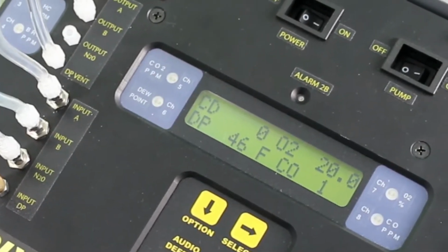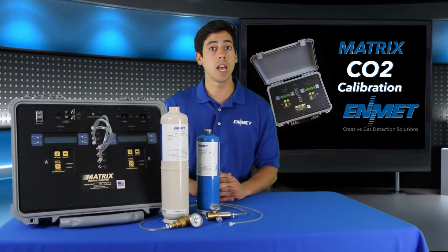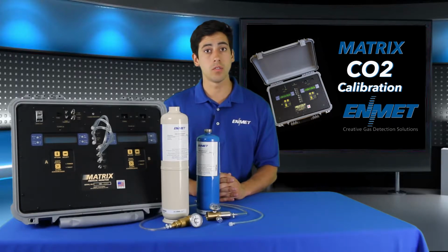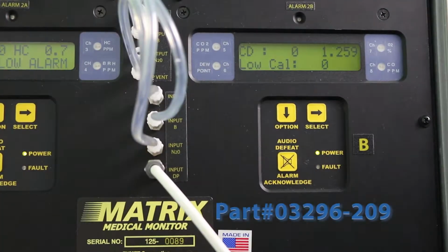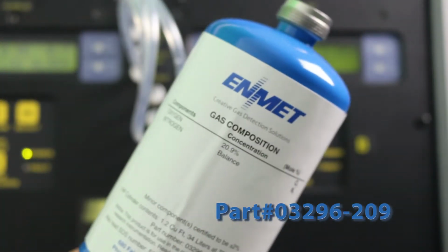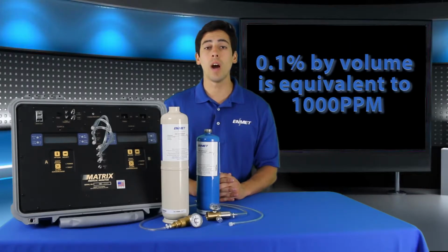Depending on the model, CO2 can be on either side A or B. The CD shown on the screen stands for carbon dioxide. Before you start, you'll need two different gases for this calibration: 20.9% oxygen for the zeroing and 1000 ppm CO2. Each of these gases will require a different regulator.